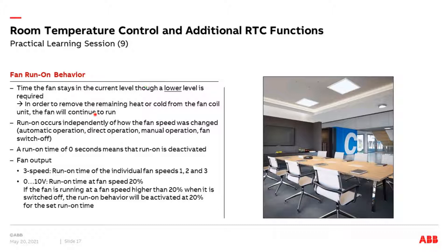The run-on behavior means that the fan stays in the current level if a lower level is required. For example, when the fan is in speed number three and we switch it off, it stays in fan speed number three for several seconds, then fan speed number two, then fan speed number one — to blow out the remaining heat or cold from the fan coil unit. This is also a feature which I want to show you later.